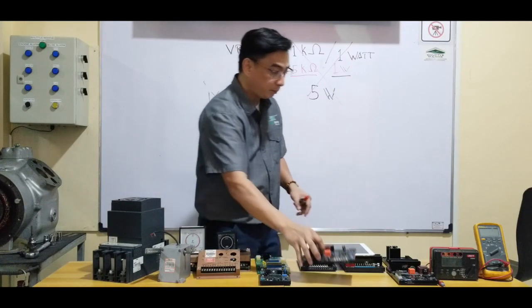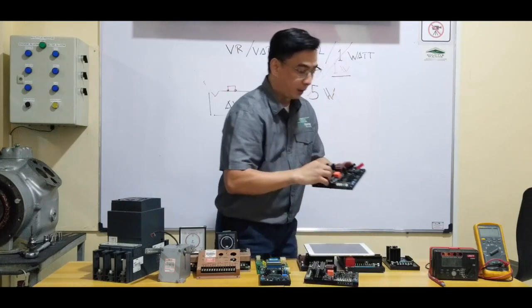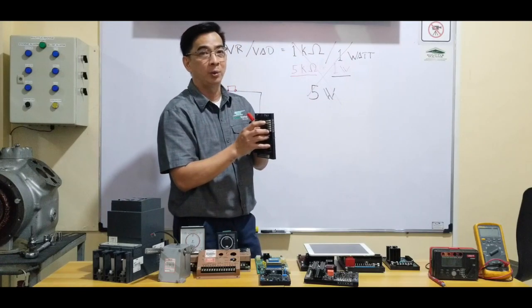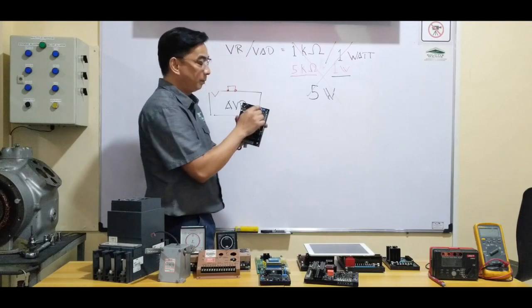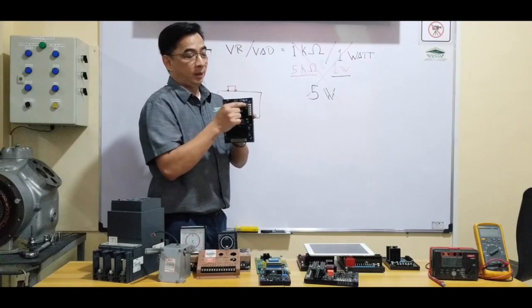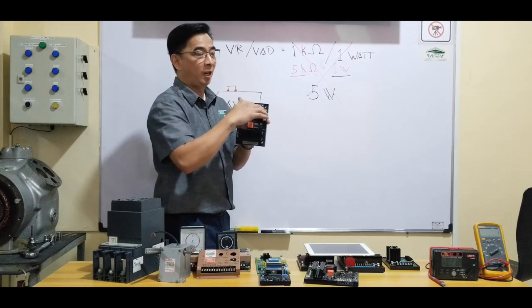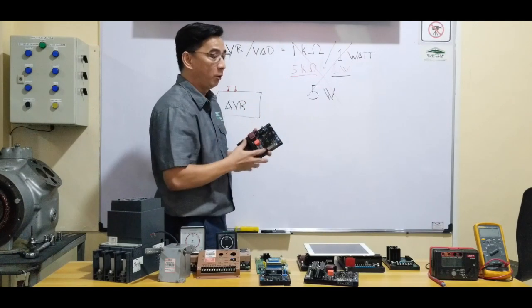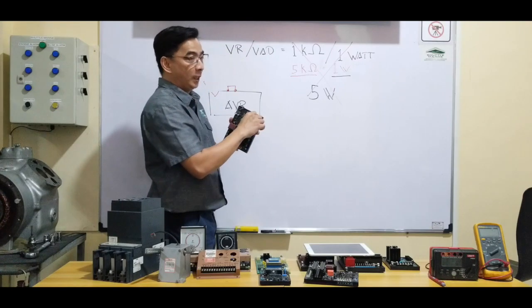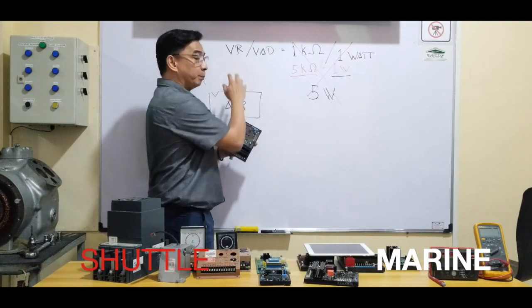So every AVR, it has a potentiometer jumper or link together. So if I don't have a remote adjustment, that link stays there. But if I have an optional remote on the switchboard or whatever location on your facilities or onboard the vessel, then we need to remove this and install the potentiometer.